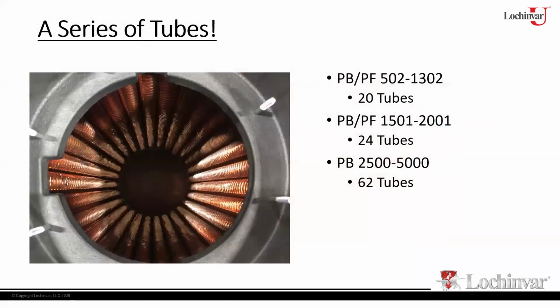As I mentioned, a lot of tubes here, right? For the 500 to 1.3 million, 20 tubes; 1.5 to 2 million, 24. And then when you get to the larger models, 62 tubes. There's a lot of tubes in those bigger models. So how do we get 62 tubes in this thing? Basically, we're adding dual coils, right? Each one of these copper tubes can only handle so many BTUs. So to be able to get up to 5 million BTUs, we have to have more surface area of the heat exchanger. So to do that, we add more tubes.